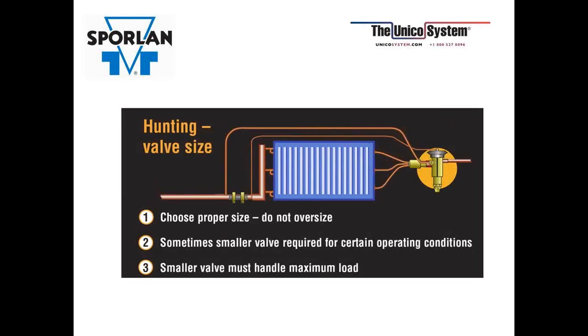Choose a proper size, don't oversize. Sometimes a smaller valve is required for certain operating conditions, but then you've got to make sure that that smaller valve is also still big enough to handle the maximum load.